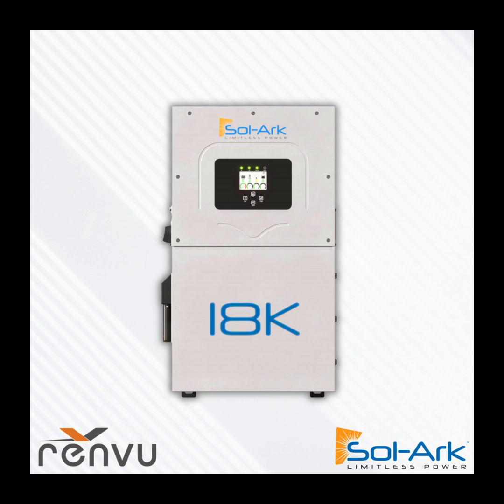What I'd say is don't think about a commercial project like you do residential. With residential, you do whole home backup, and you can do whole building backup with a Sol-Ark commercial system. It's actually not difficult, because we include the grid relays into each inverter and they're scalable. You just take the size of the service, scale up the inverters, spec out general panel boards, and use that to wire everything together. So it's certainly possible and very accessible to do large, multiple-inverter, whole-building-backup systems with Sol-Ark. But I would not neglect essential backup and load-side connections for commercial.